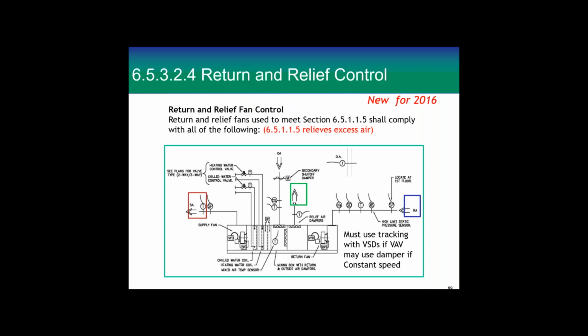Return and relief fan shall comply with the following. And what this says is that you're going to track, your return fan is going to track with an offset your supply air fan.